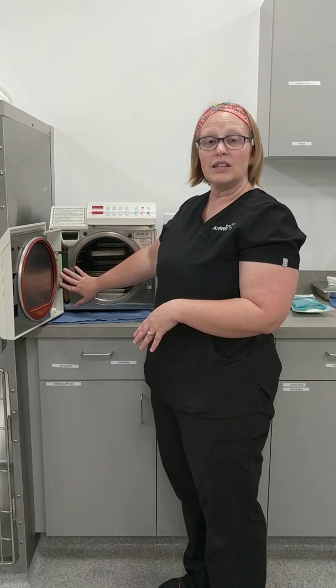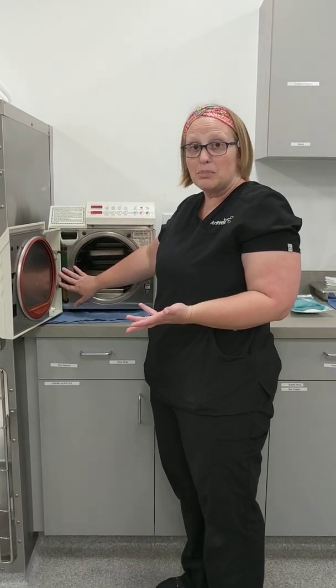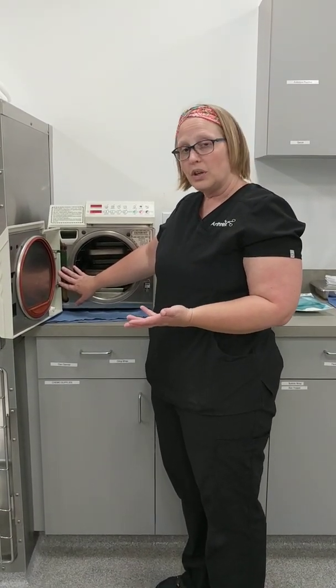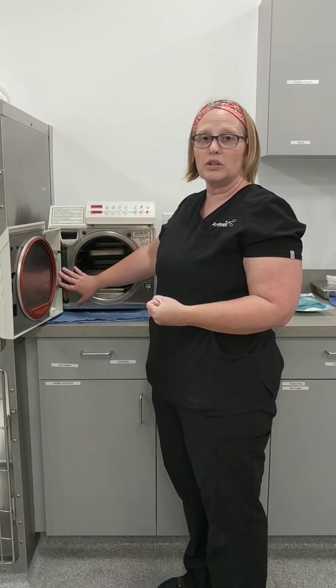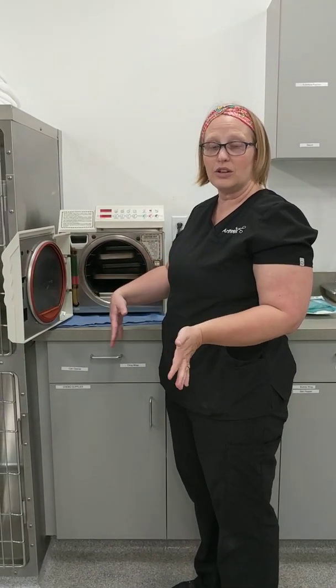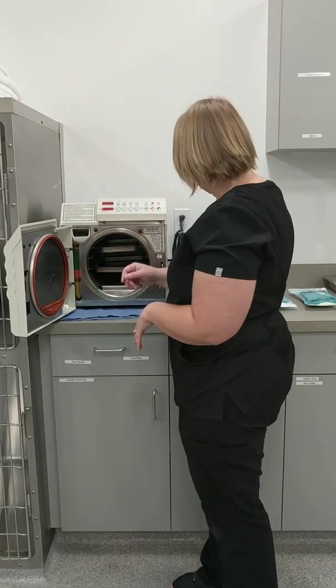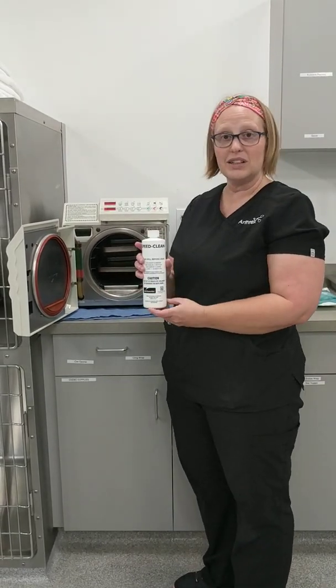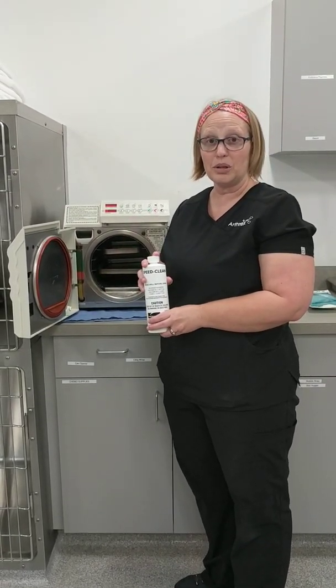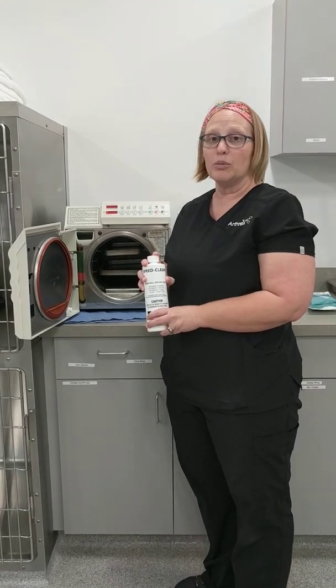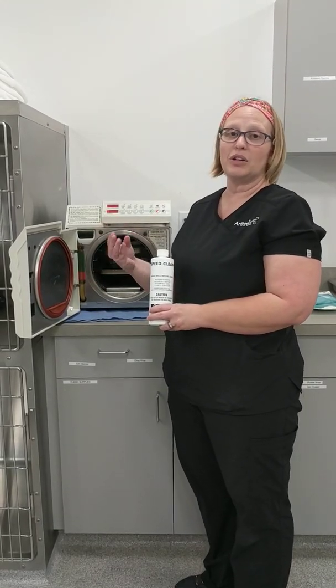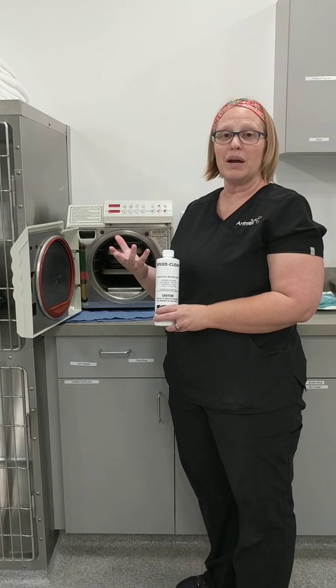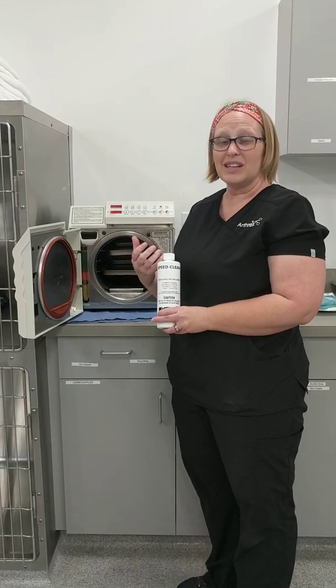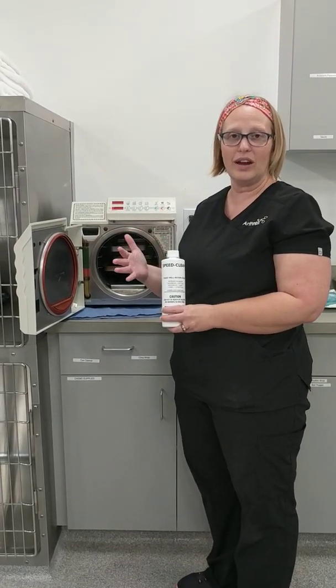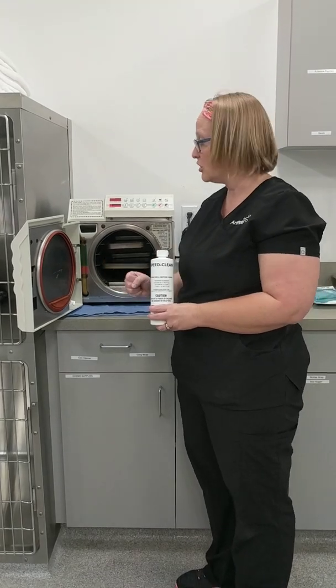This autoclave gets cleaned a couple of times a month, so we don't do a whole lot of surgery here, but enough to warrant doing this at least twice a month. It cleans out your line, gets fresh water, and it also allows you to use your Speed Clean, which is the only product I recommend for cleaning your autoclaves for multiple reasons. It really gets any buildup or gunk or any slime that might get in there, mold, mildew, things like that. No good. If you have those, then you're not really sterilizing your instruments.